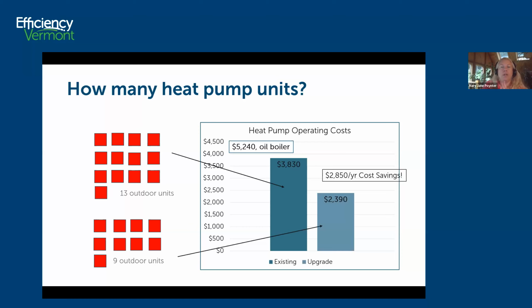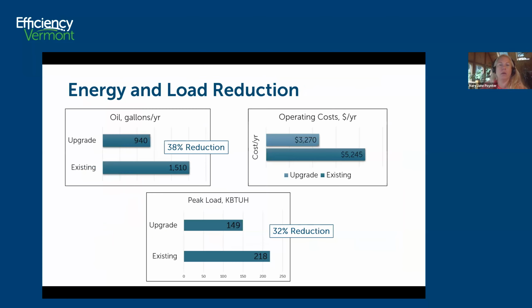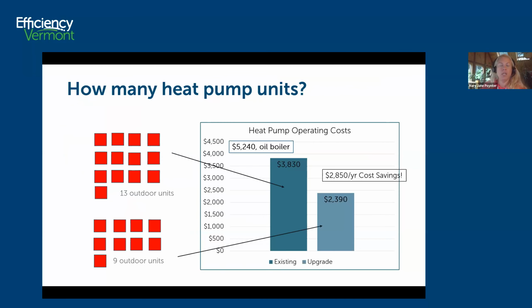Okay. Operating costs. So if you were to stick with the existing system, or excuse me, the existing load, which was 213 or 113? 218. So the existing load is 218. You would need about 13 2-ton units. I assume that the 2-ton units were doing about, I don't know, 16,000 BTUs instead of 24,000 BTUs at 5 degrees or 0 degrees. If you do the air sealing and insulating, your load has dropped. Now you can go to 9 outdoor units to meet the needs of your building.